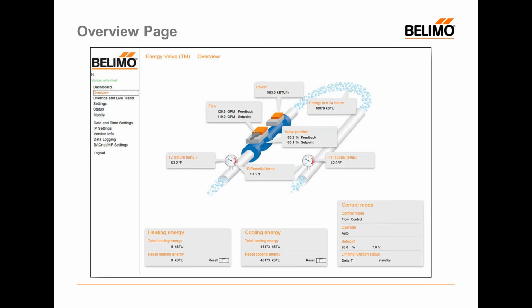You can see if the valve is being overridden. And when I say if the valve's being overridden, that means if the override has been done locally by someone before you tying into the valve via the WebView access. So there's a way to override the valves either via WebView or maybe BACnet. So it's slightly different than, say, overriding your analog output to 10 volts DC.